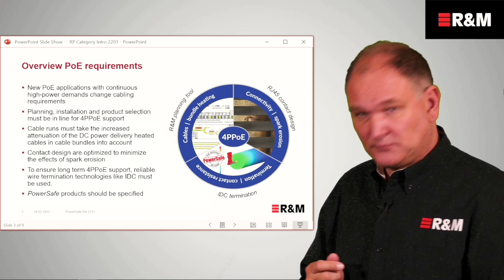Now introducing the remote power categories. The installation standards ISO/IEC 14763-2 and EN 50174-2 specify new RP categories and define that these categories have to be used in order to comply with the standards. An RP category, in essence, defines the average current that's allowed in a bundle of cables. We have 3 RP categories, 1, 2, and 3. RP1 allows currents up to 212 milliamps in the bundle, whereas RP3 allows up to 500 milliamps overall. For all applications, the maximum current is defined as 500 milliamps per wire.